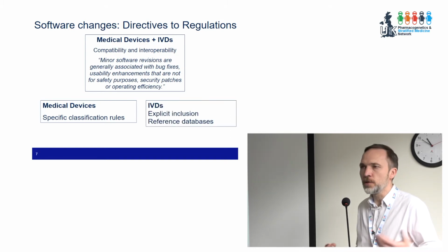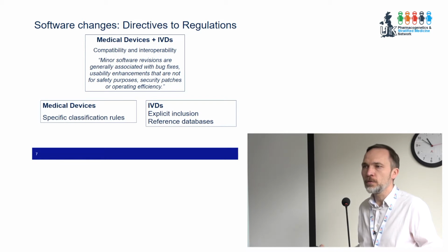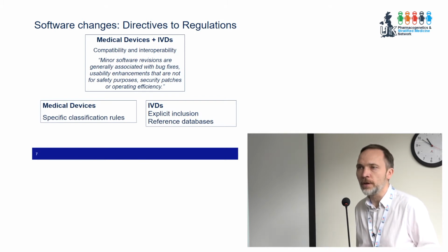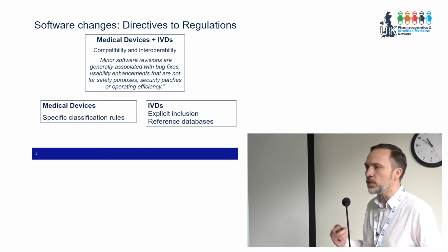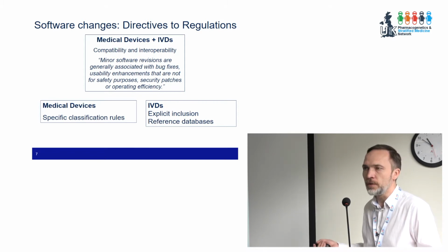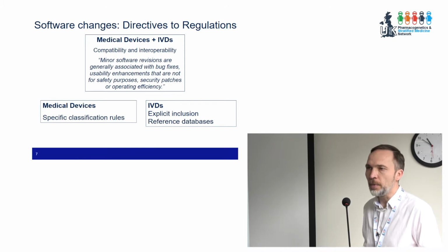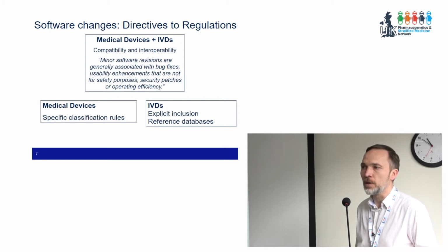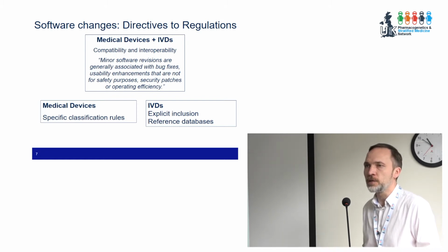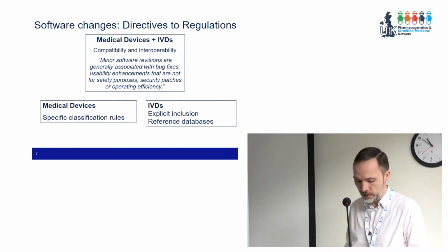And for IVDs, some people thought that software couldn't be an IVD, that there's no such thing as IVD software. Well, that's not true. And that was implicit in the directives. It's now explicit in the regulations. Yes, software can be an IVD, and also for some reason in the IVD regulations, but not in the medical device regulations, there's reference to reference databases, and they need to be characterised, and we need to understand which reference databases are being used with the IVD.